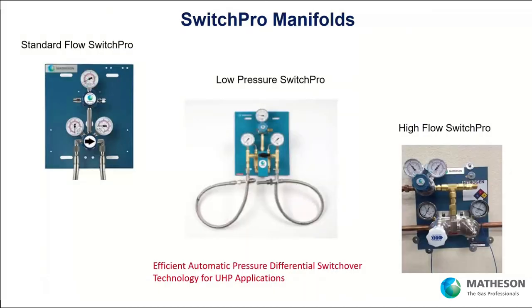What if you just want to be cost-effective and need a switchover in a cabinet? Maybe you're dealing with hydrogen — flammable from 4% to 75%, that's dangerous — or methane, or a hydrocarbon. These are all pressure differential switchover systems: one side delivers while the other waits patiently for the first side to run empty and then takes over, up through the line regulator to your point of use. For low pressure delivery around 40 to 60 psi with something like propane, a different but still pressure-differential panel is needed. And if you need something equivalent to 15 CFM nitrogen, now you need a larger manifold panel — which can also be housed in a cabinet.